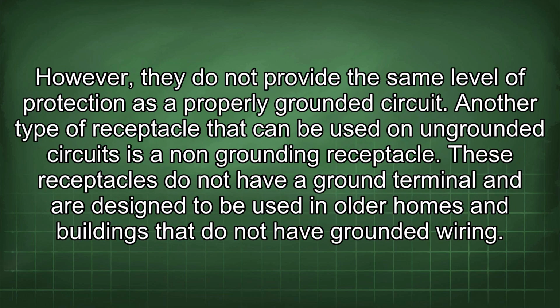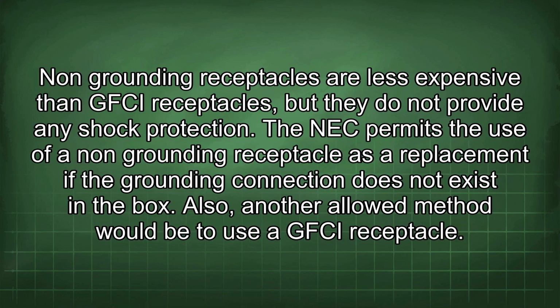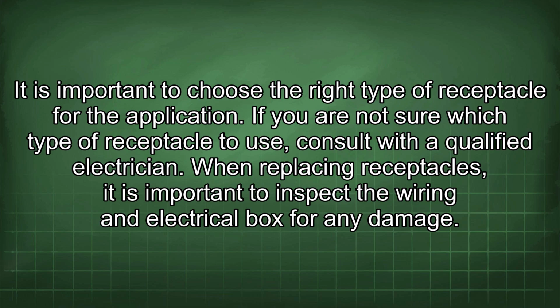However, they do not provide the same level of protection as a properly grounded circuit. Another type of receptacle that can be used on ungrounded circuits is a non-grounding receptacle. These receptacles do not have a ground terminal and are designed to be used in older homes and buildings that do not have grounded wiring. Non-grounding receptacles are less expensive than GFCI receptacles, but they do not provide any shock protection. The NEC permits the use of a non-grounding receptacle as a replacement if the grounding connection does not exist in the box. Also, another allowed method would be to use a GFCI receptacle. It is important to choose the right type of receptacle for the application. If you are not sure which type of receptacle to use, consult with a qualified electrician.